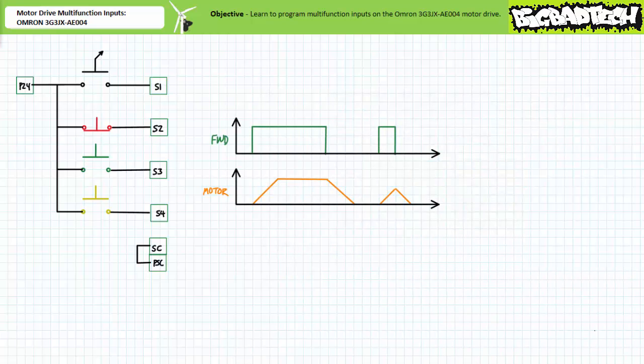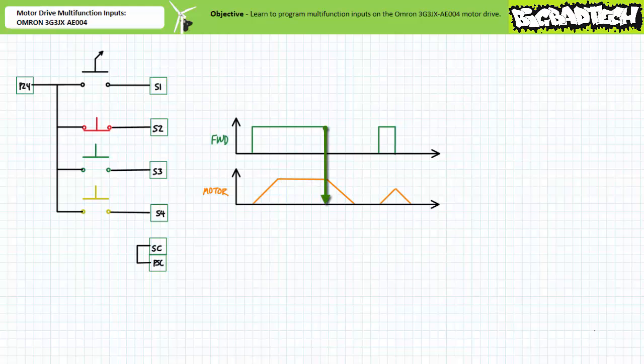A timing diagram of the forward function would look like this. When the input executing the forward function is energized, the motor drive initiates the acceleration ramp up. If the input remains asserted, the motor drive will continue to operate at constant speed mode. When the input executing the forward function is de-energized, the motor drive initiates a deceleration ramp down, at which point it turns off. The motor drive will only reach constant speed mode if the input executing the forward function is energized longer than the acceleration ramp up. When de-energized prior to reaching constant speed, the motor drive initiates an abbreviated deceleration ramp down.